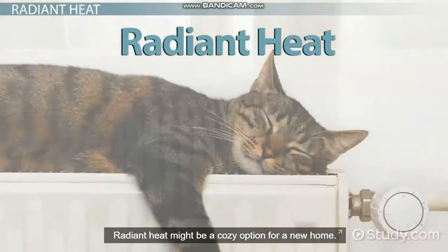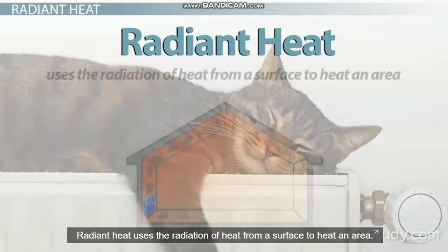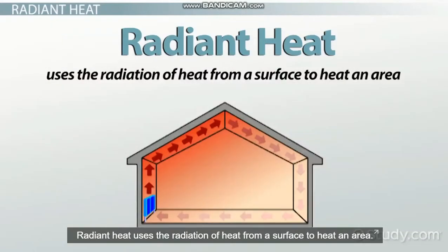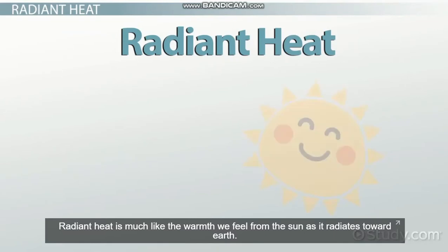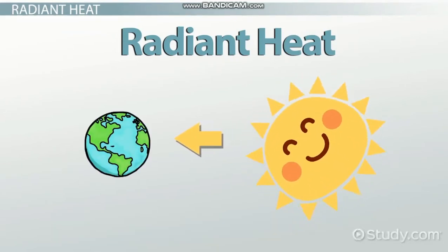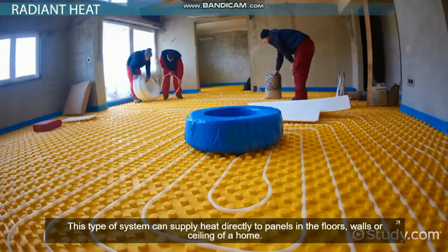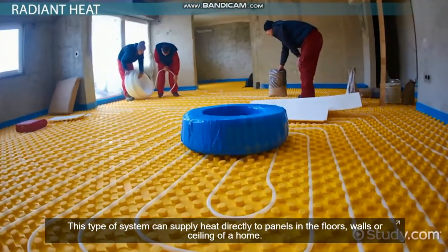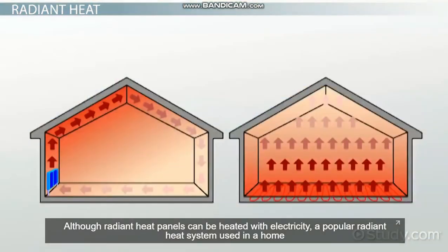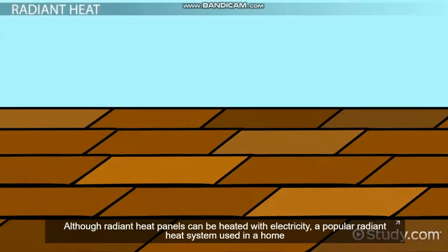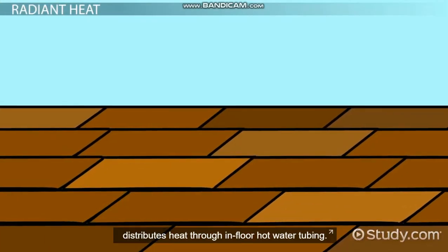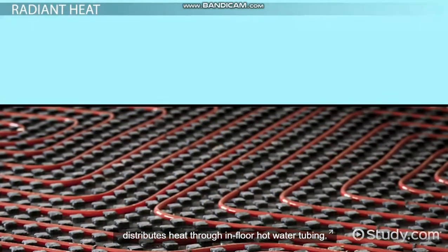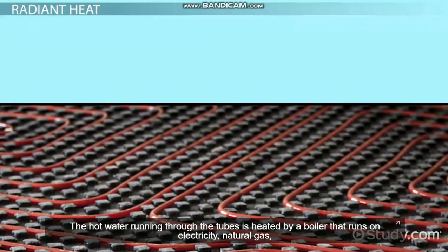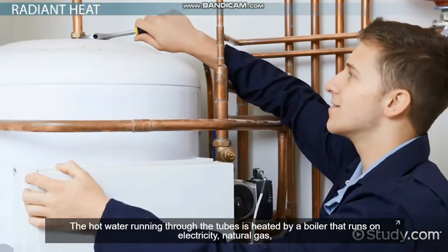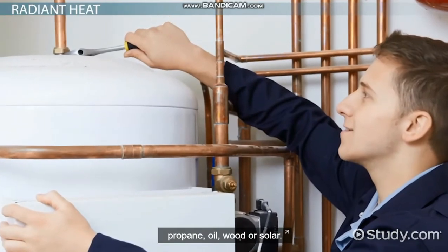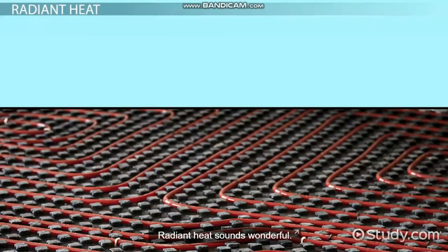Radiant heat might be a cozy option for a new home. Radiant heat uses the radiation of heat from a surface to heat an area. Radiant heat is much like the warmth we feel from the sun as it radiates toward Earth. This type of system can supply heat directly to panels in the floor, walls, or ceiling of a home. Although radiant heat panels can be heated with electricity, a popular radiant heat system used in a home distributes heat through in-floor hot water tubing. The hot water running through the tubes is heated by a boiler that runs on electricity, natural gas, propane, oil, wood, or solar.